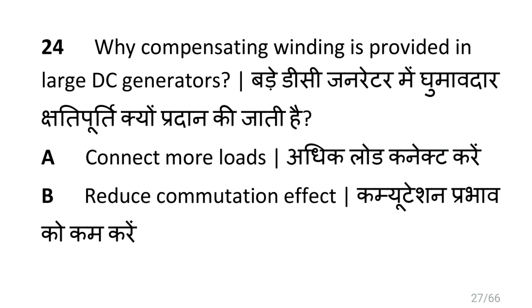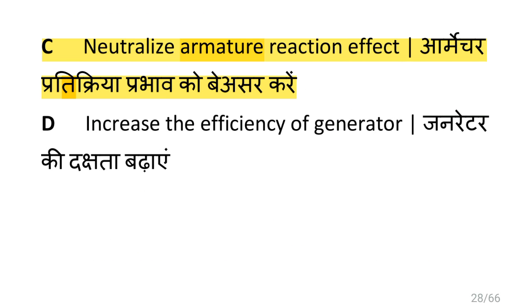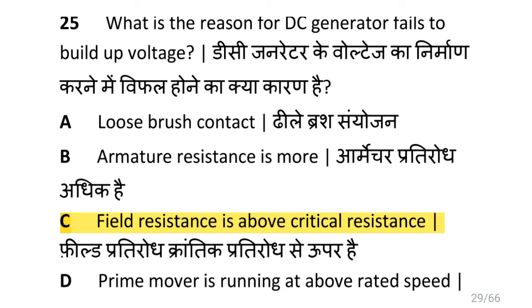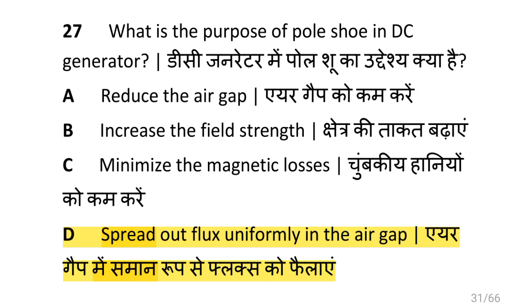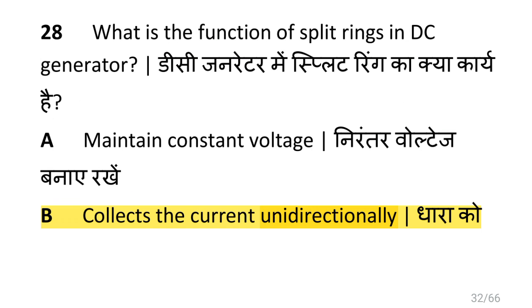Why is compensating winding provided in large DC generators? That is to neutralize the armature reaction effect. What is the reason a DC generator fails to build up voltage? That is field resistance is above critical resistance. What is the name of the generator if its field is connected in parallel with armature? That is shunt generator. What is the purpose of pole shoe in DC generator? That is to spread out flux uniformly in the air gap. What is the function of split ring in DC generator? That is to collect the current in one direction.